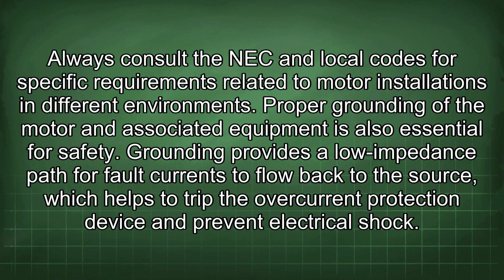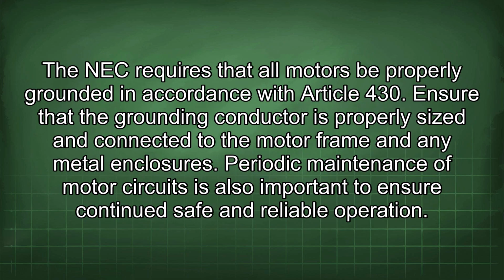Proper grounding of the motor and associated equipment is also essential for safety. Grounding provides a low impedance path for fault currents to flow back to the source, which helps to trip the overcurrent protection device and prevent electrical shock. The NEC requires that all motors be properly grounded in accordance with Article 430. Ensure that the grounding conductor is properly sized and connected to the motor frame and any metal enclosures.